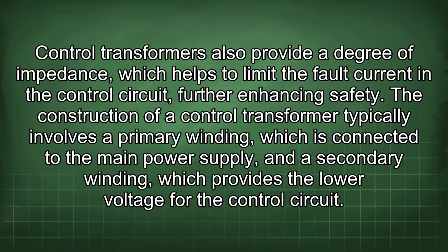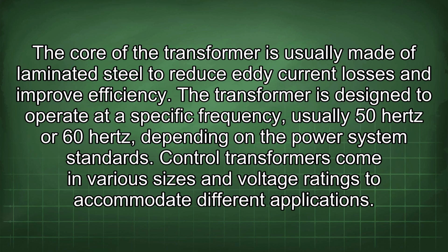The construction of a control transformer typically involves a primary winding which is connected to the main power supply, and a secondary winding which provides the low voltage for the control circuit. The core of the transformer is usually made of laminated steel to reduce eddy current losses and improve efficiency. The transformer is designed to operate at a specific frequency, usually 50 Hz or 60 Hz, depending on the power system standards. Control transformers come in various sizes and voltage ratings to accommodate different applications.